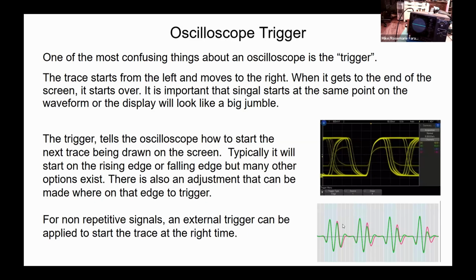And so some of the newer scopes for sure, like the one I'm going to be demonstrating here, doesn't have a lot of this ability. But a lot of times you can change where your sync level is. So on a pattern like this, I might raise my horizontal sync line right up to just catch right up at the top here, and then I'm going to say sync on a rising edge relative to this spot. And then all of a sudden the pattern is going to start showing correctly and it'll look good because I'm catching the same piece of the waveform every time. If they all go to the same peak, unfortunately, you're not going to have that luxury. But again, it's really about repetitive signals.